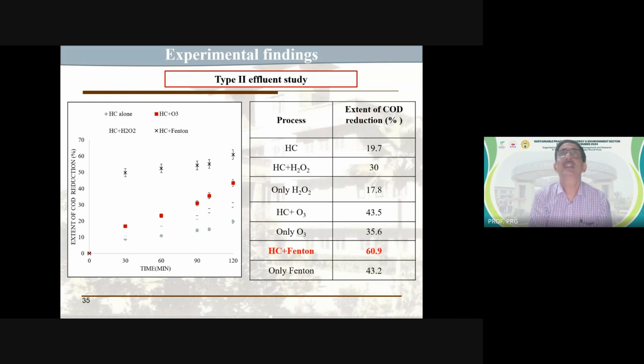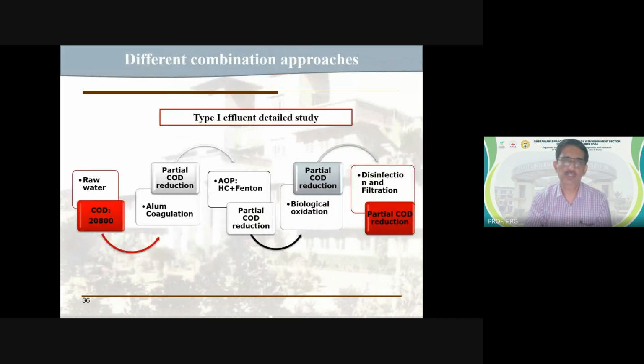So if I'm looking at a COD level of maybe 1 lakh or 2 lakh, advanced oxidation may not work at all. In that case, you might have to look at a different treatment scheme, for example wet air oxidation can be tried. But at about 40, 50, 60,000 as the initial COD, as you can clearly see here, the treatment is possible.